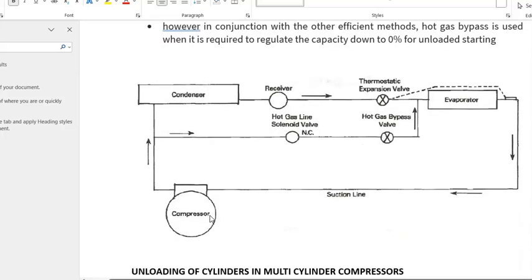Here you will see the compressor, suction line, and discharge line going to the condenser. From the discharge outlet of the compressor, one branch line goes from here. This is the hot gas line with a normally closed solenoid valve. Then it goes to the hot gas bypass valve. It will come to the evaporator inlet, and from the evaporator inlet, to the suction line.